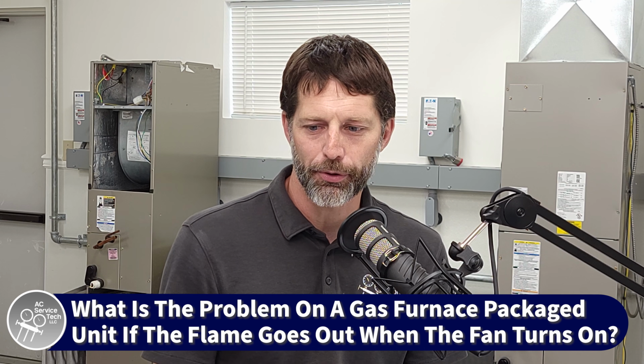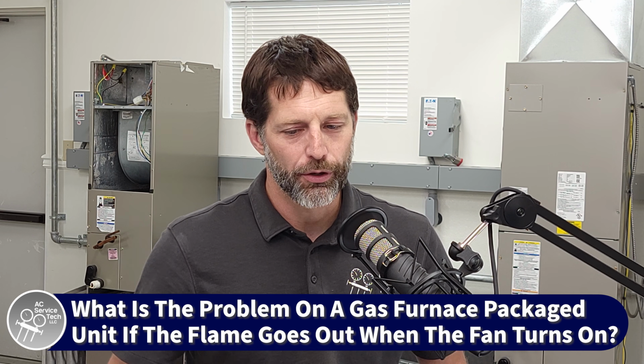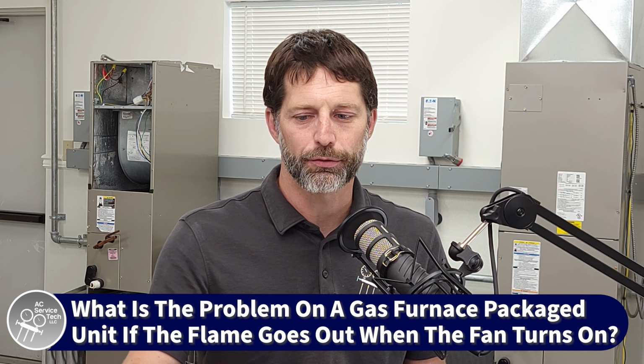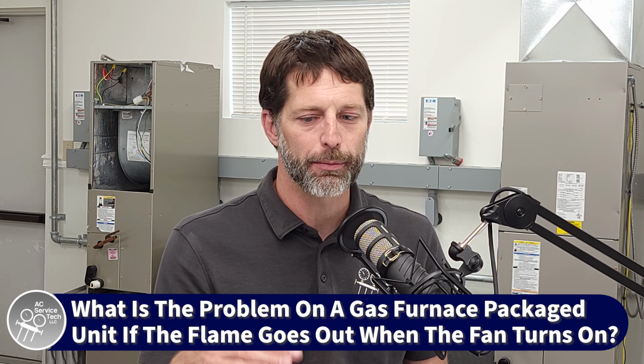Absolutely. Yeah, great. Agreed. We have a technician named James, and he's asking a more specific question. Carrier package unit burners won't stay lit when I put the burner panel back on. So while going through the heat sequence, as soon as the indoor blower comes on, the flame goes out. Heat exchanger is okay, no cracks, and new foam tape around heat exchanger. When the burner panels are removed, the unit operates as designed.